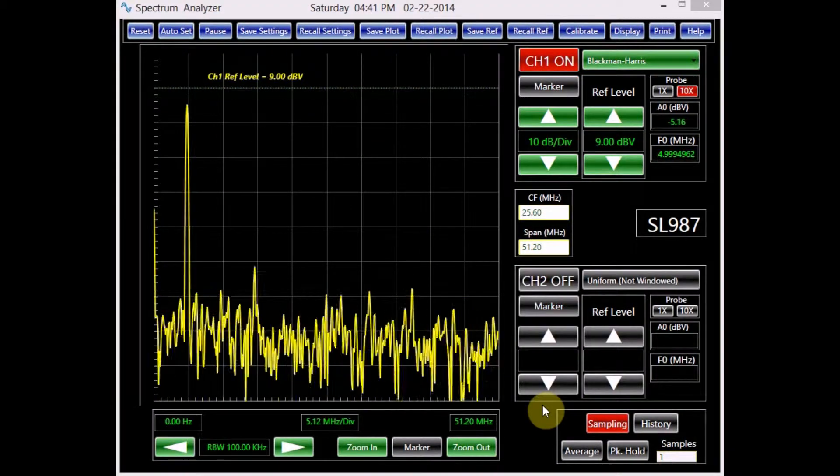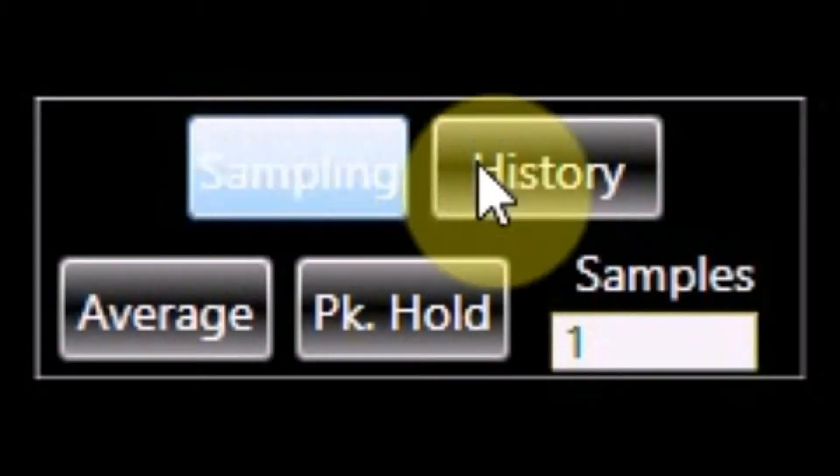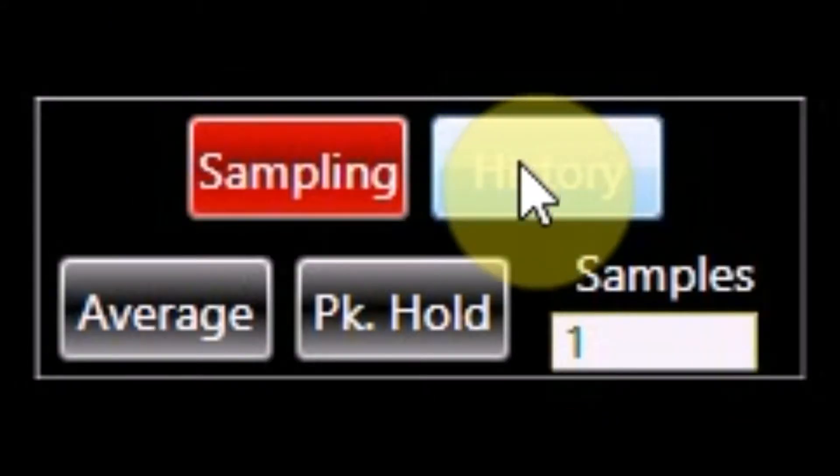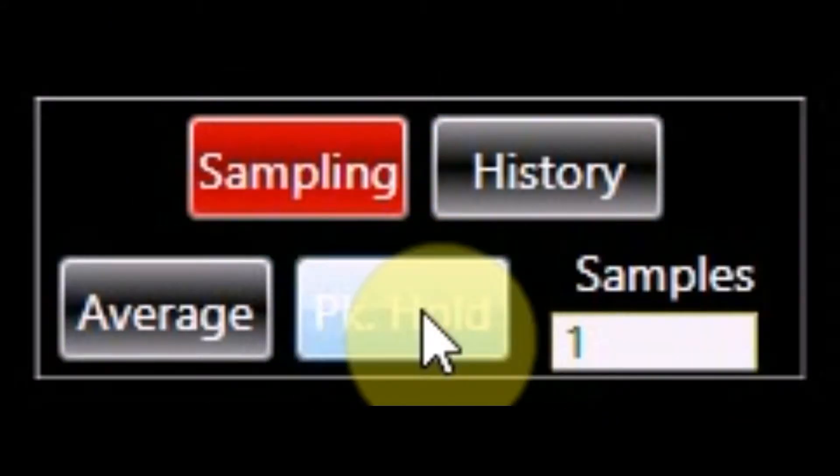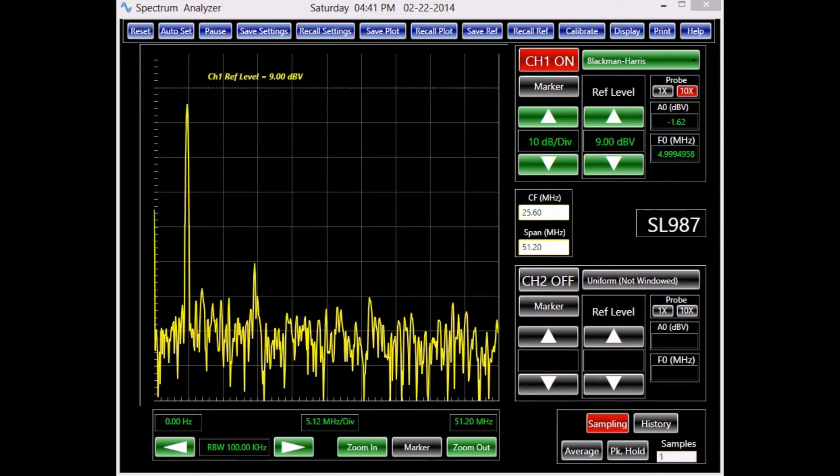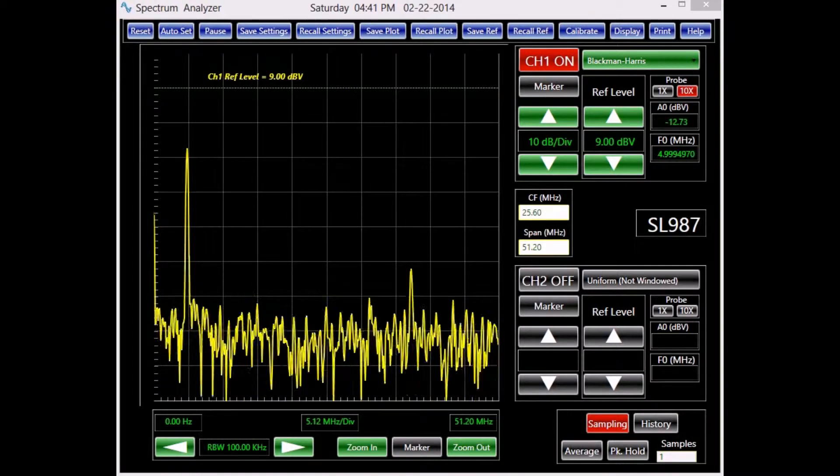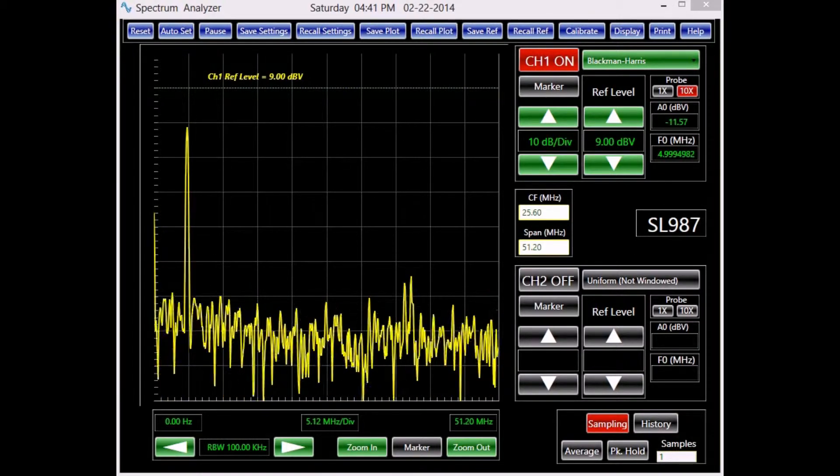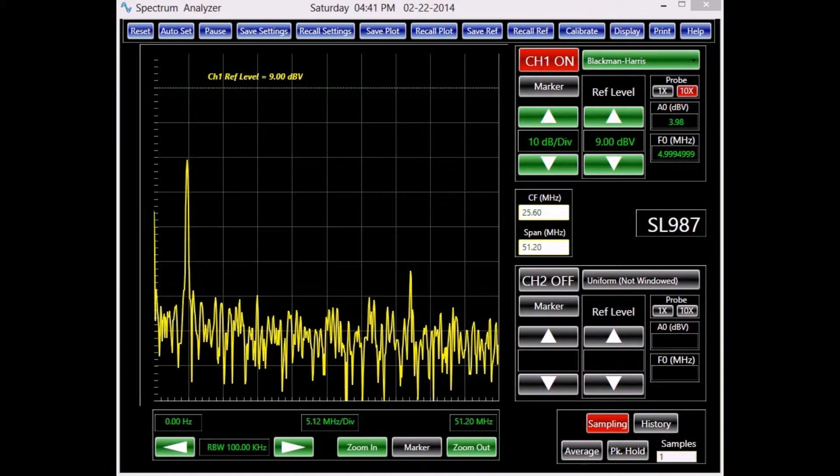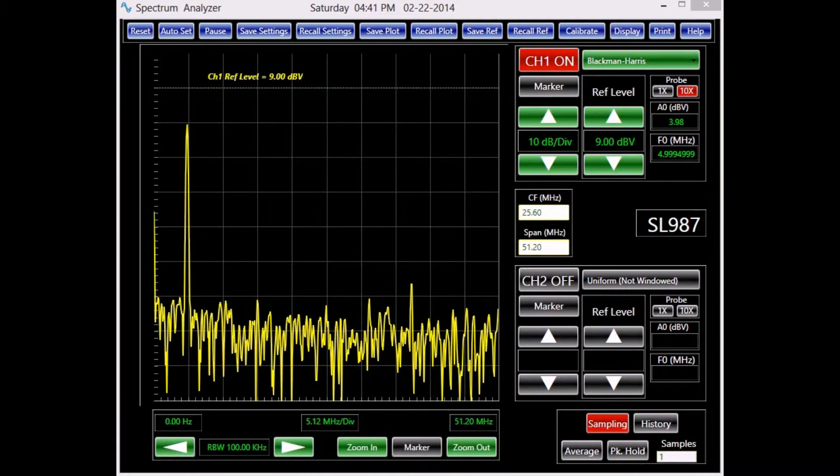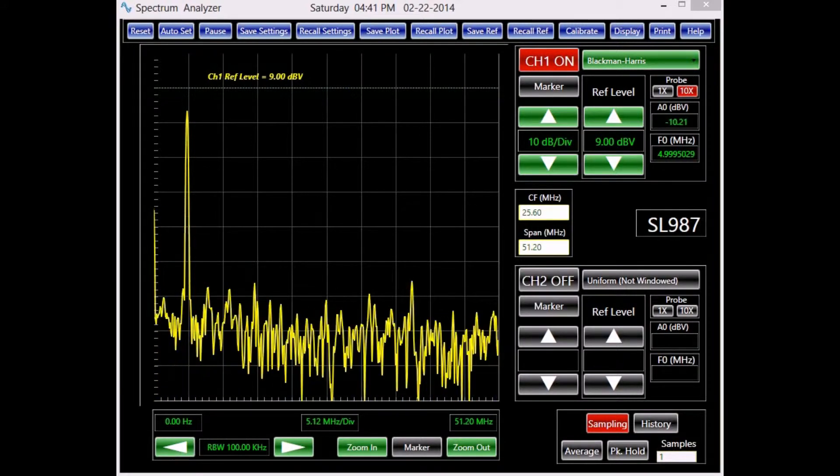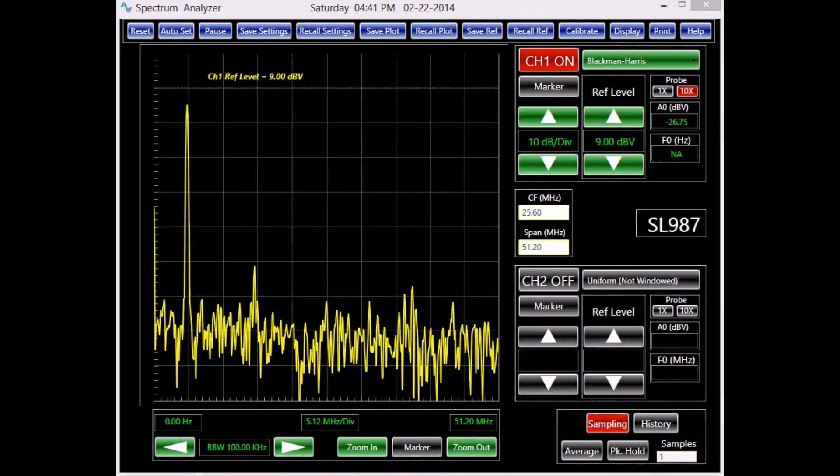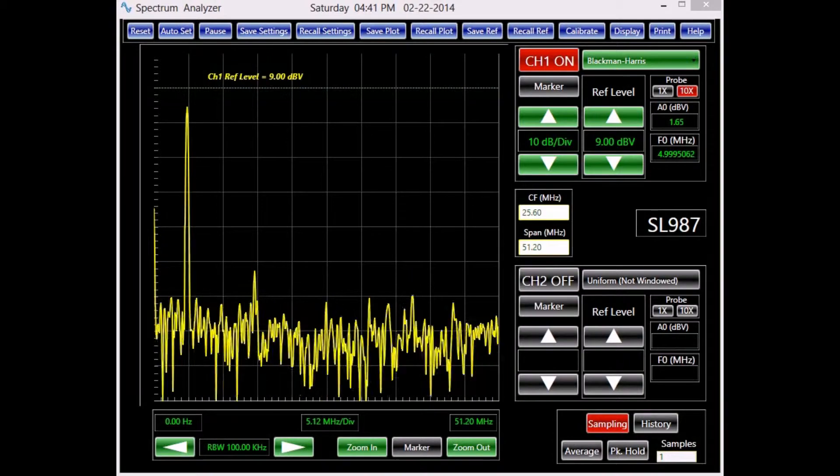The data acquisition panel features sampling, history, average, and peak hold modes. The sampling mode, the mode we have been using up to now, performs the FFT process on some portion of the data in the buffer memory and plots its amplitude spectrum on the screen. The information between the selection points is lost.